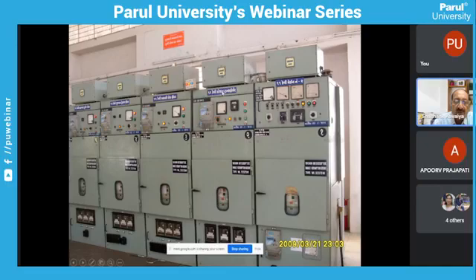See, the name of the panel is also affixed on the backside, so that if someone wants to take line clear on this feeder, he may not make a mistake from the backside, because if someone is working on the backside, then he will get shocked. You got me? If I'm taking line clear of this feeder, my person has to work on this feeder. If someone says, okay, let me clean the backside also, and instead of this panel he goes to that panel, he will definitely get a shock, he will die. You may not understand this from these pictures, but on a live substation visit you can ask questions and know the system, and if feasible, your management and I can take you to some substation also.